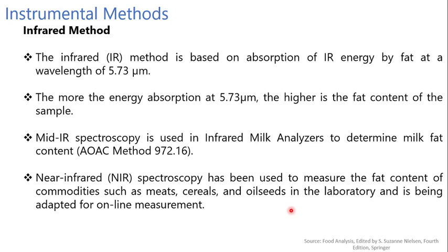The more the energy absorption at 5.73 micrometer, the higher is the fat content of the sample. Mid-IR spectroscopy is used in infrared milk analyzers to determine the milk fat content.